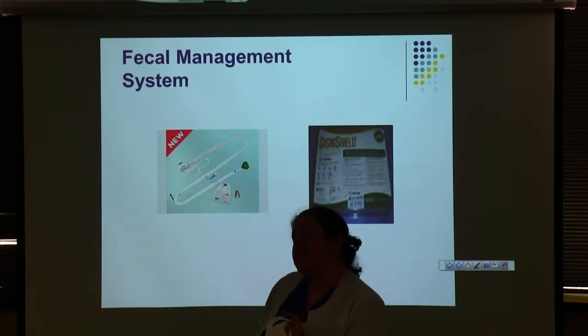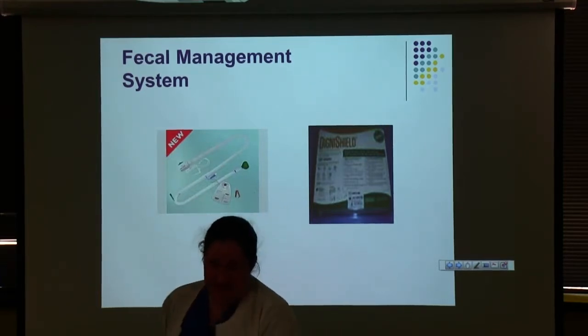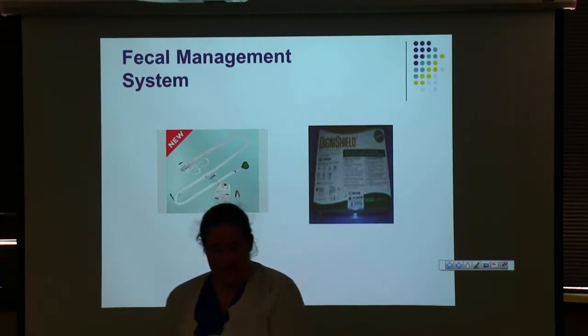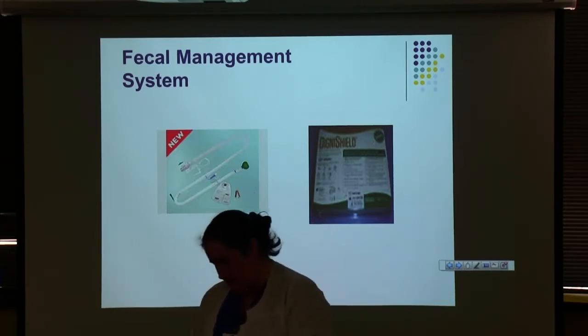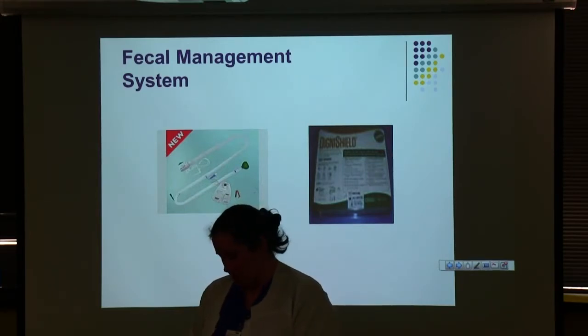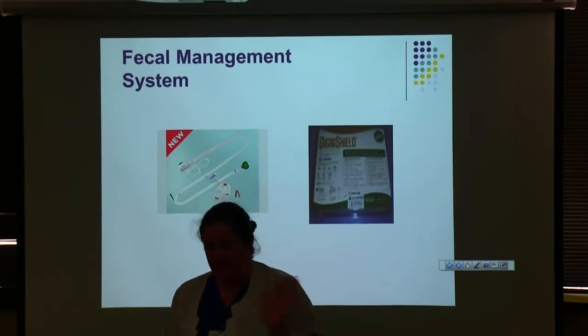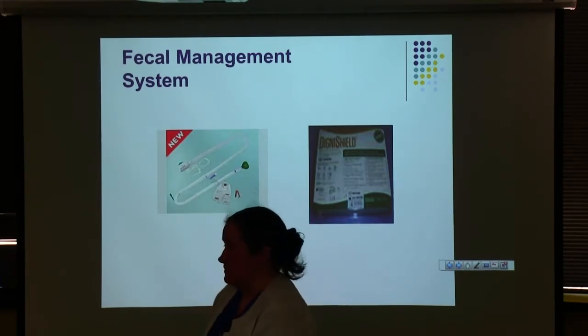The device is one size — your patient just needs enough rectal tone to hold it in place, which can sometimes be an issue. The bags themselves are available in materials management. Like a Foley catheter, this device is held in place by a balloon — but it's designed so the balloon does not press against the rectal mucosa like a Red Rubber catheter balloon would. It's much gentler. Your syringe comes marked with 45 ml — that's exactly how much water the balloon is meant to hold. No more, no less.